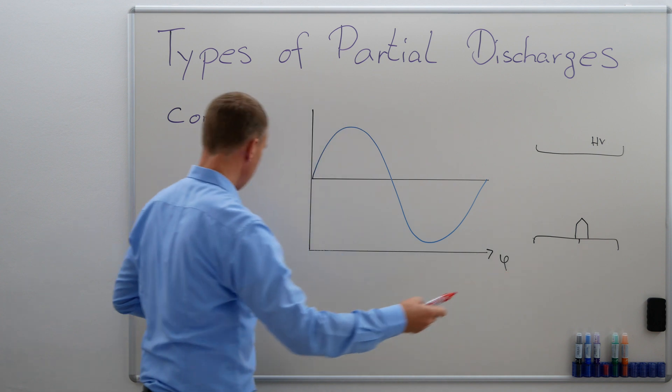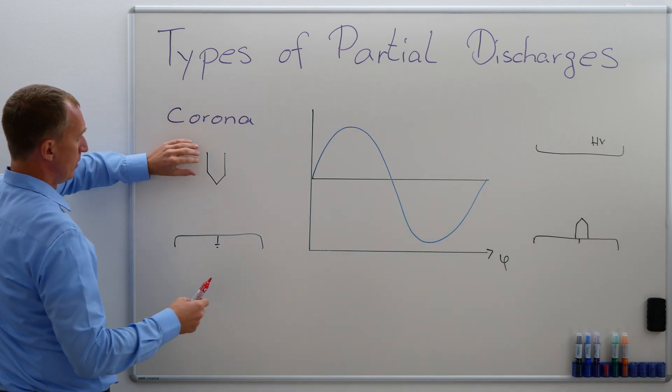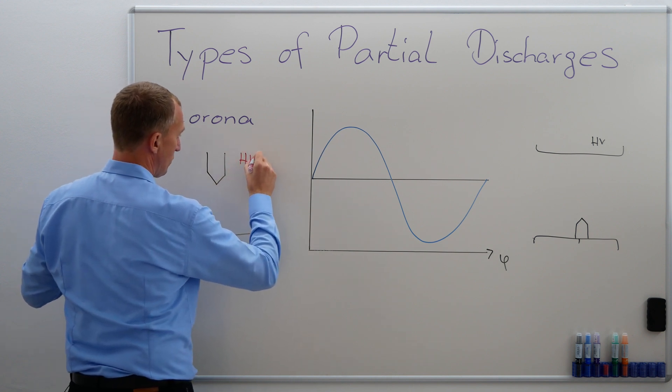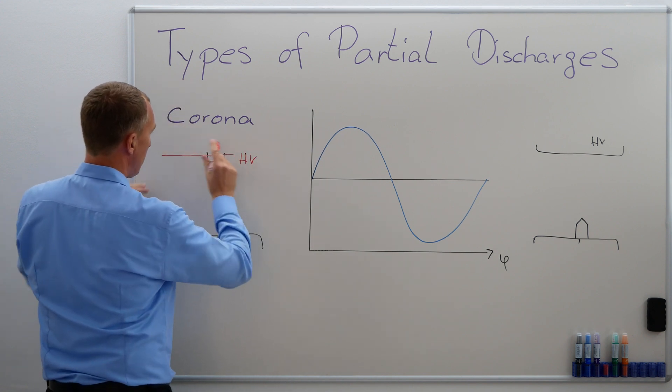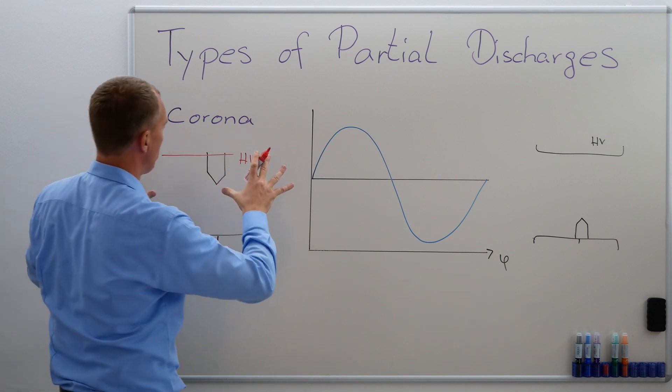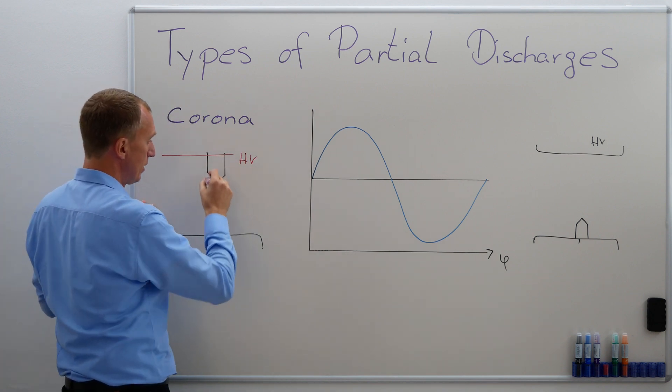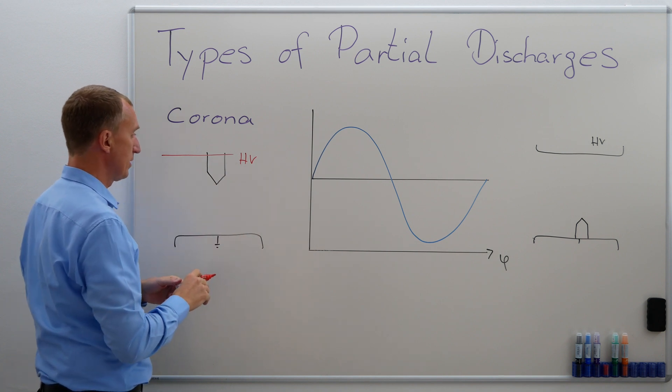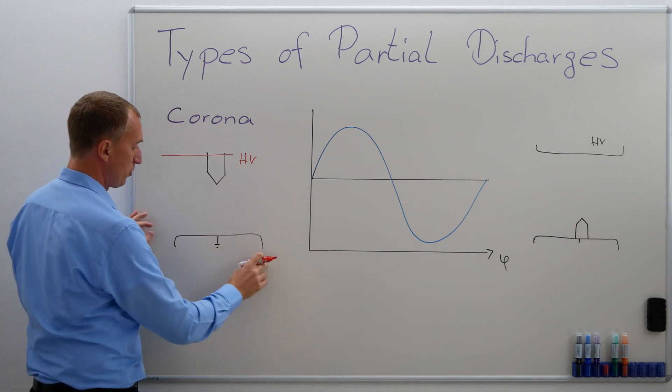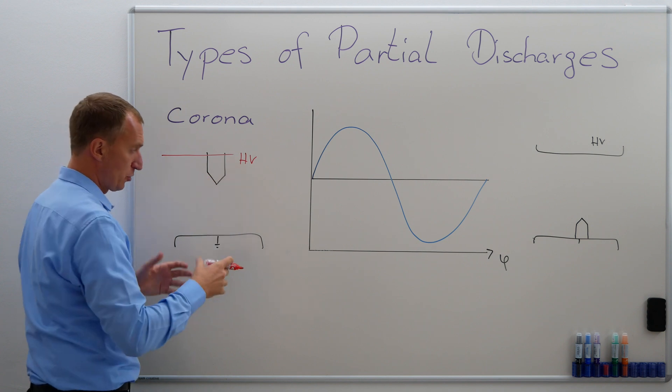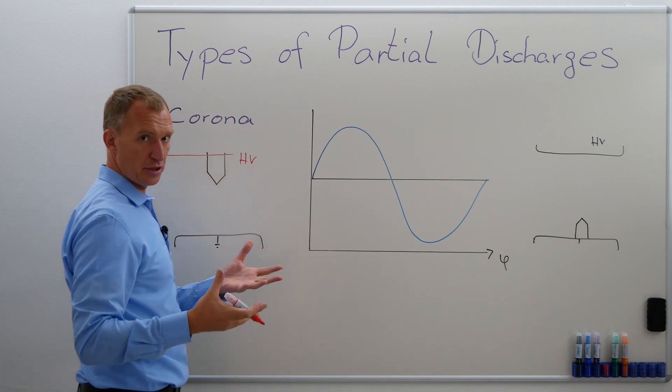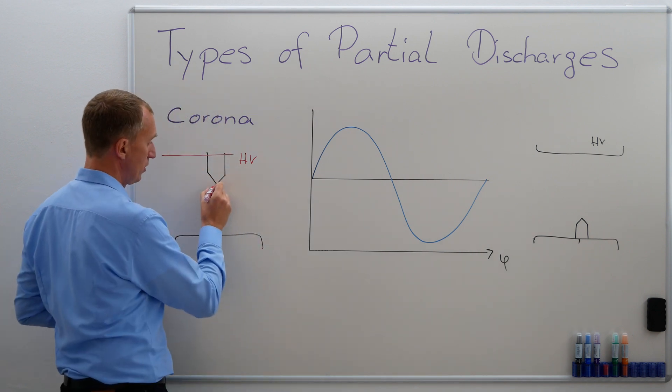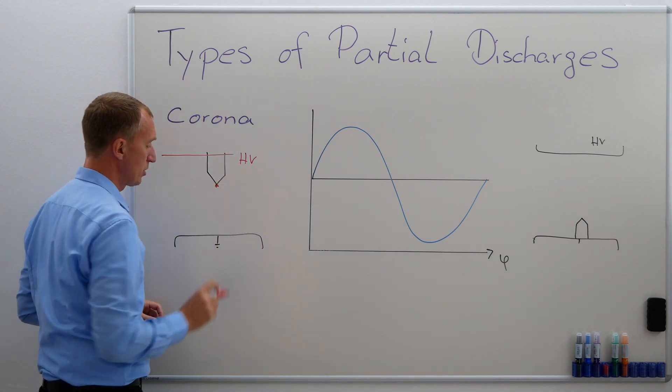First of all, let's say that I'm having a pointy or a tippy high-voltage conductor. And this would be HV. Obviously, usually I have many things on high-voltage, right? But there's one little tippy part like a screw or like a bolt or like a piece of conducting tape or whatever. And I have my ground plate. And if I'm increasing the voltage and I'm reaching a voltage which is above partial discharge inception voltage, I'm going to have partial discharges.